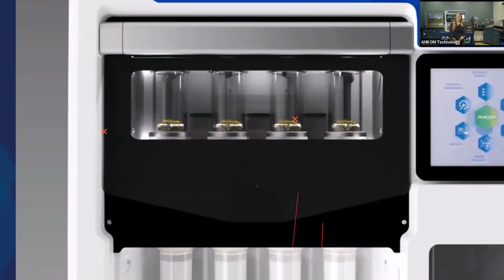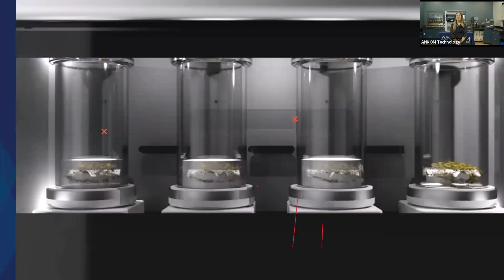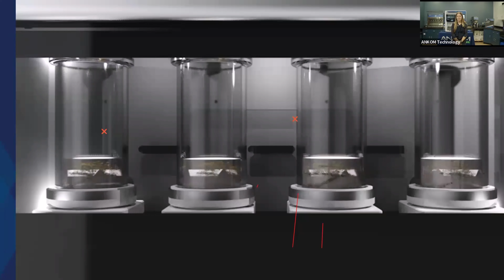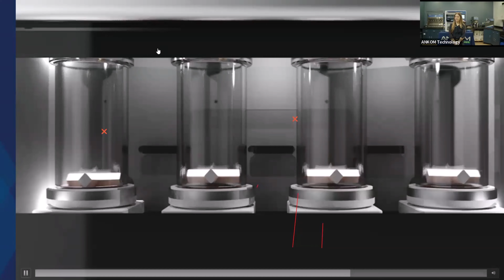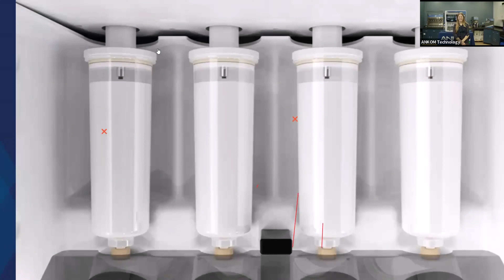To protect sensitive analytes and eliminate contamination, the digestion vessel headspace and SPE columns are purged with nitrogen. Once the system is free of oxygen, reagents are pumped into each vessel while the sample is mixed. Digestion time, temperature, and pressure are monitored and controlled while mixing. Since no manual transfer of sample is required between the saponification, extraction, and evaporation steps, transfer error is eliminated and precision is improved. After saponification, the sample solution is cooled and transferred through specially designed filters into the SPE column.